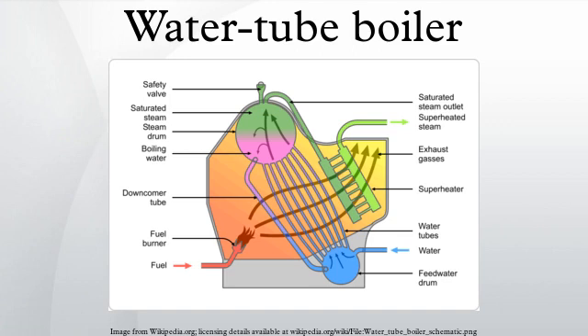A significant advantage of the water tube boiler is that there is less chance of a catastrophic failure. There is not a large volume of water in the boiler nor are there large mechanical elements subject to failure.